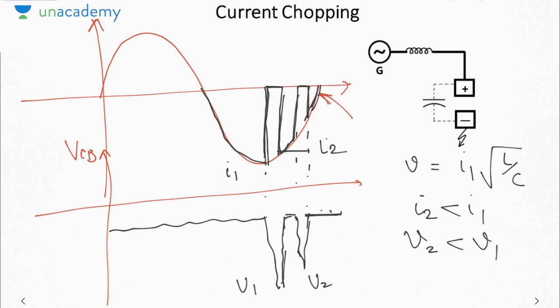Because if we interrupt the arc before the current reaches 0, then a high voltage, called the prospective voltage, is induced across the circuit breaker, which will again ionize the medium between the plates to initiate the arc. Or we can say the electromagnetic energy stored in the inductor for non-zero current, which is equal to half L I square, gets converted to the electrostatic energy of the circuit breaker, causing high voltage across the plates. So if somehow we can reduce this electromagnetic energy, or reduce its conversion to electrostatic energy, we can reduce the prospective voltage.